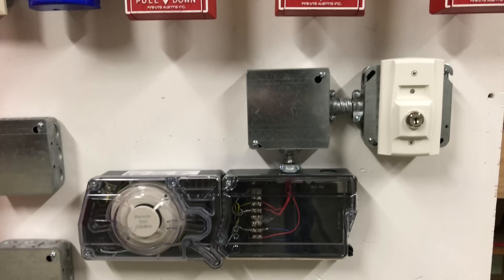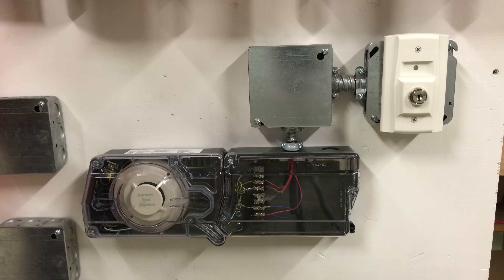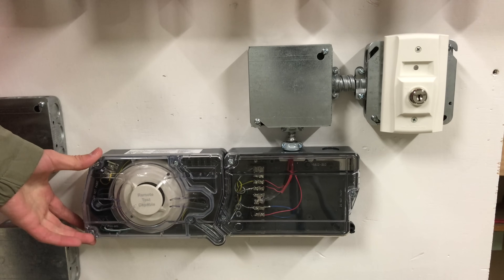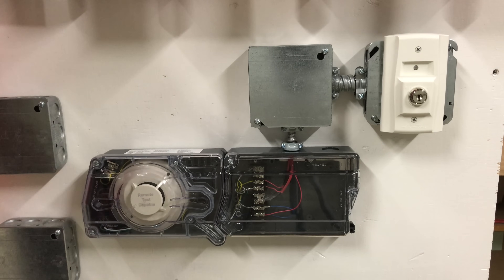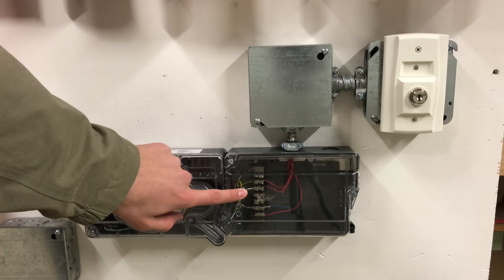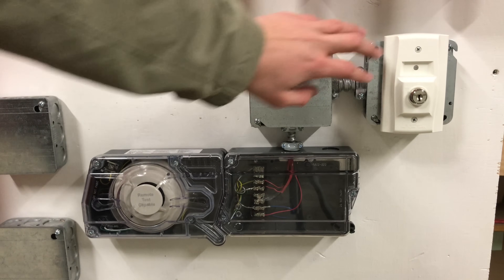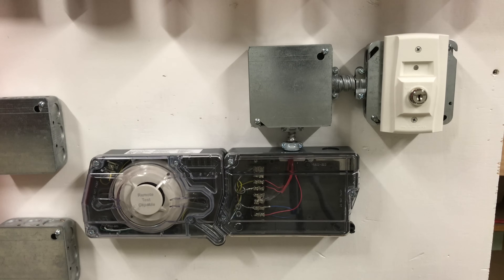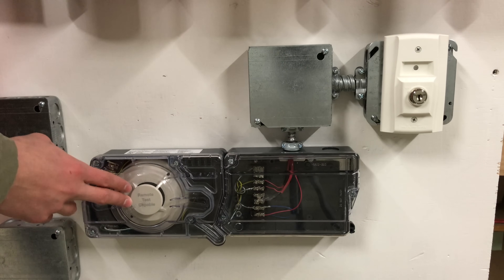Below the BG10s, there's something I think is really cool — a FireLite D355PL addressable duct detector. These are special smoke detectors meant to monitor air ducts. As you can see, we have a junction box where wires come in and connect to the duct detector. To the right of the junction box is a System Sensor RTS151 key switch. This allows me to test and reset the duct detector remotely, which is really nice since these detectors are sometimes mounted in ceilings.